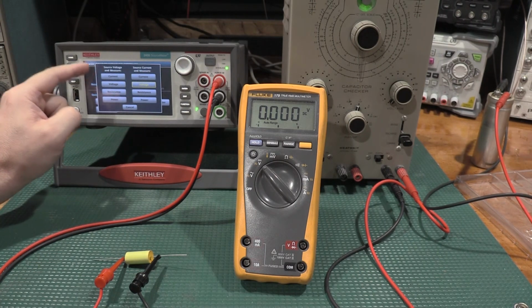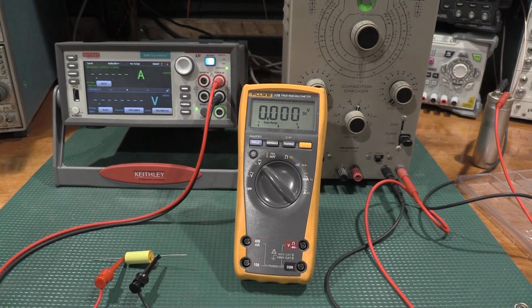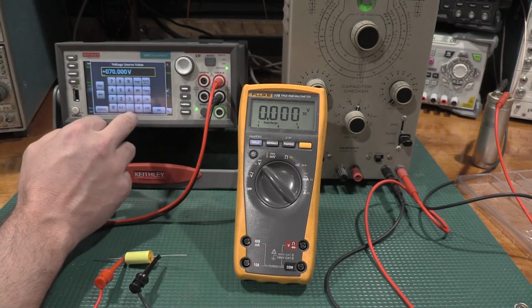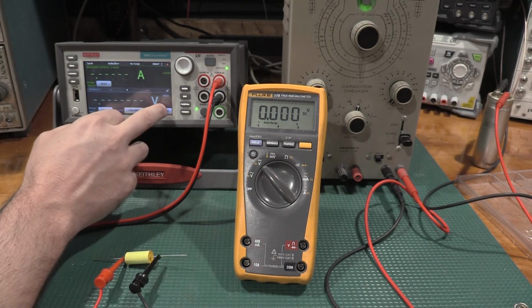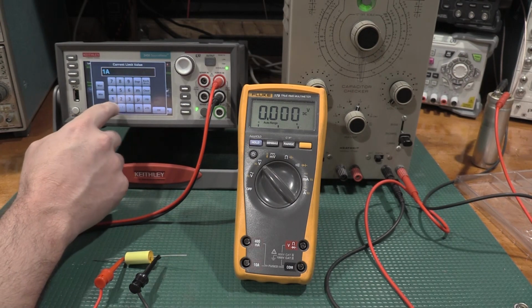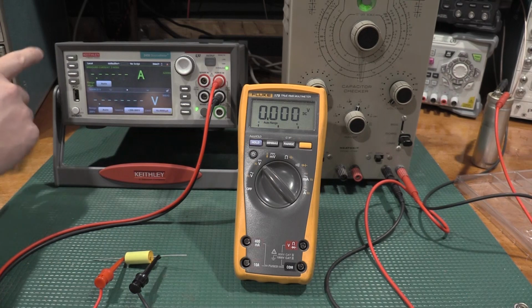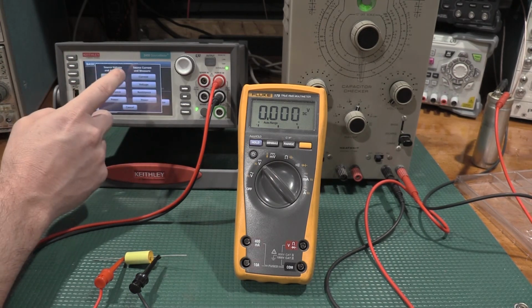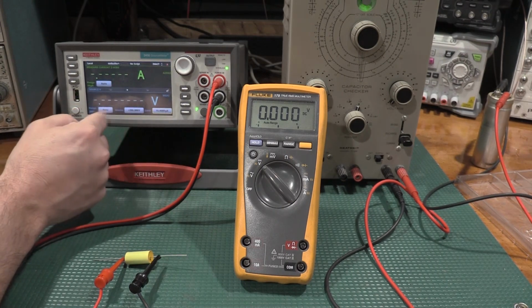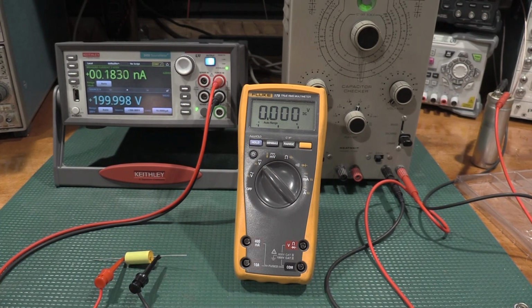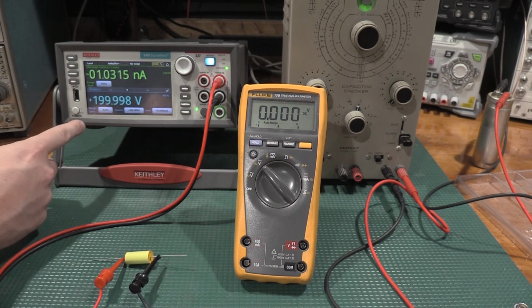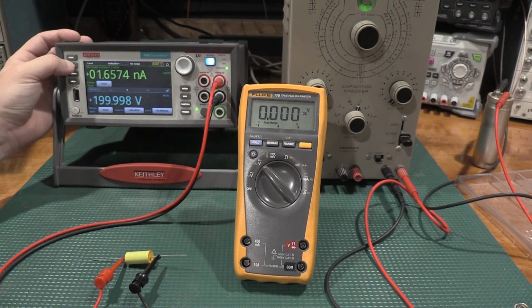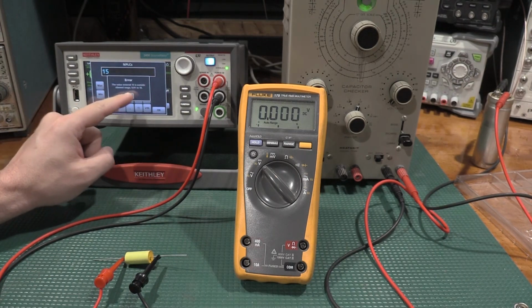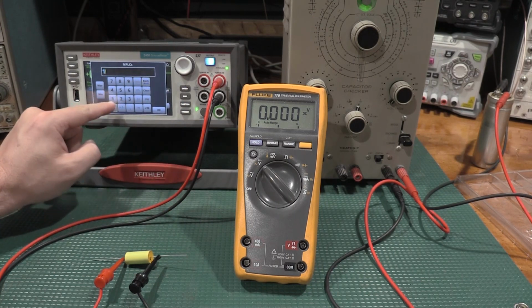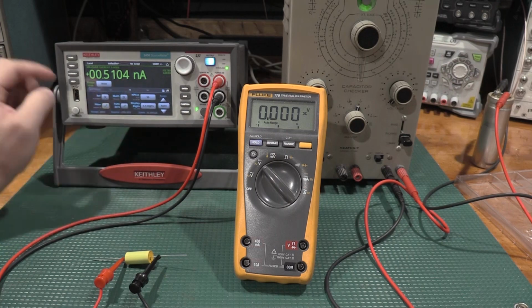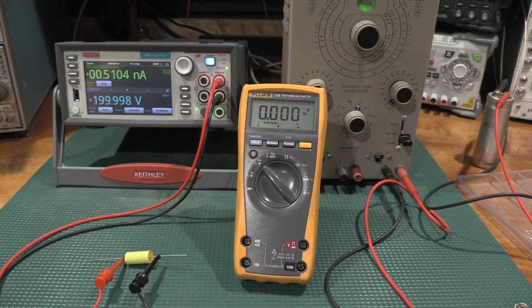So let's source voltage and measure current. And, oh yeah, 200, okay. Limit is 10 microamp. There it goes. I wasn't reading the interlock properly because I went up to 200 volts. So let's slow this down a bit. Number of power line cycles 15. Oh, yeah, got to go to 10. It's not like with the meters. 10. And we do want to filter so we get accurate measurements. Measurements are going to be a lot slower now, but we'll get good measurements.